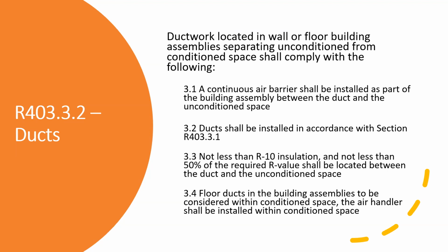If it's in a floor, or if it's just in some kind of a downturn or a furr down, and it's in contact with any part of the exterior or the attic space, the unconditioned space, it needs to have R10 insulation there. And then floor ducts in building assemblies are to be considered within conditioned space. The air handler shall also be installed in the conditioned space. So this is just talking about, again, having ducts that are not in contact with an air barrier or the outer sheathing.